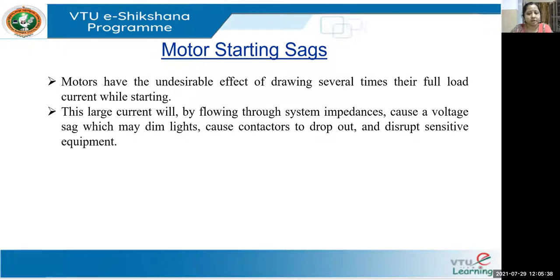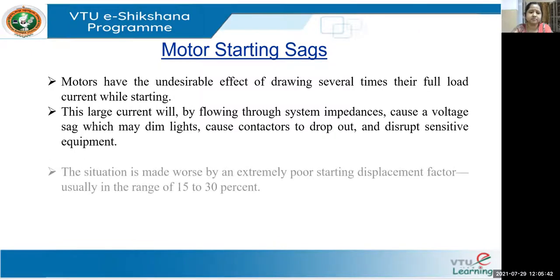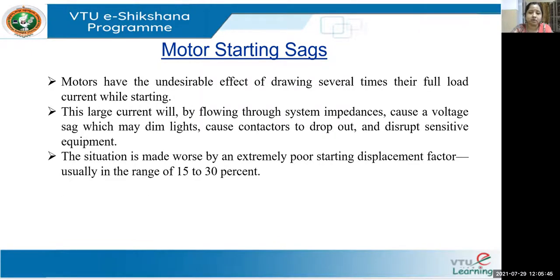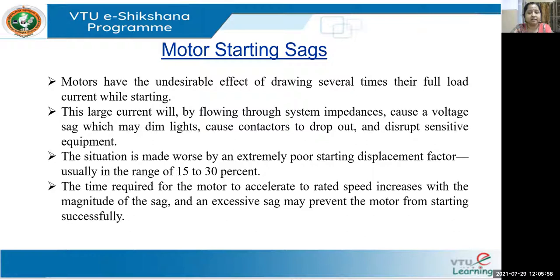The voltage dip causes contactors to drop out and disrupts sensitive equipment. The situation is made worse by an extremely poor starting displacement factor, which is usually in the range of 15 to 30%. The time required for the motor to come back to its original speed depends on motor to motor, and the time required for the motor to accelerate to rated speed increases with the magnitude of sag — it depends on both the intensity and duration of the sag. Excessive sag may prevent the motor from even starting successfully.